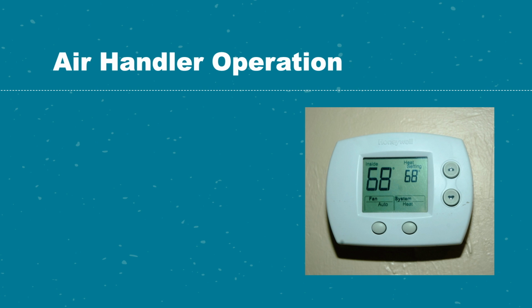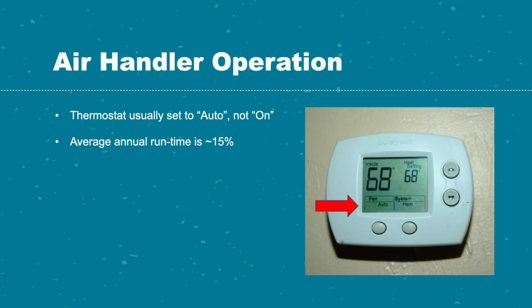Most air handlers are operated by a thermostat. This is a typical programmable thermostat that probably 90% of all HVAC systems have. And the key thing it has is a switch that allows you to set it on auto or on. And most people set their air handlers on auto, and there's good reason for that. In that case, it will only run when there's a call for heating or cooling. So that's the typical operation we see, and I'm not criticizing that. But the problem is that means the runtime is only about 15%.